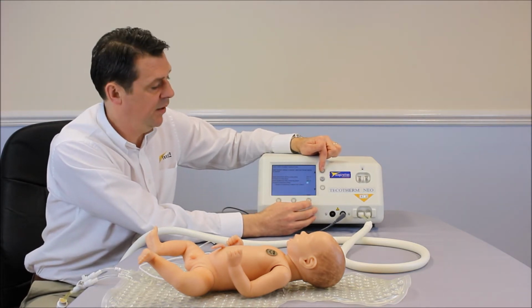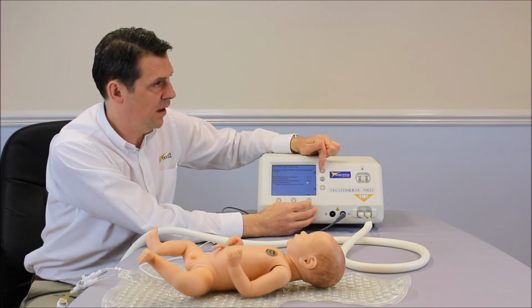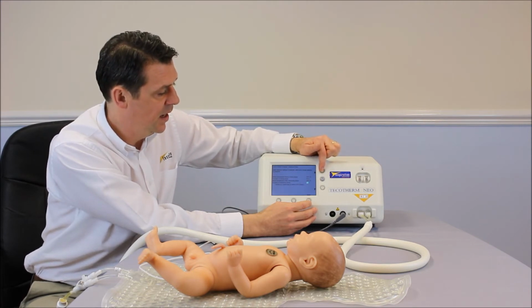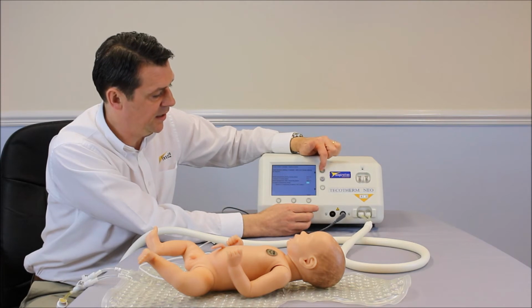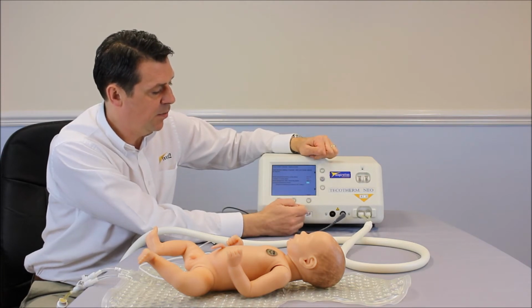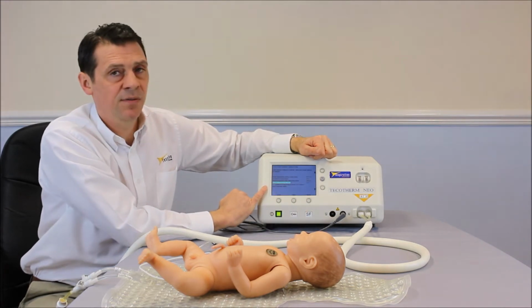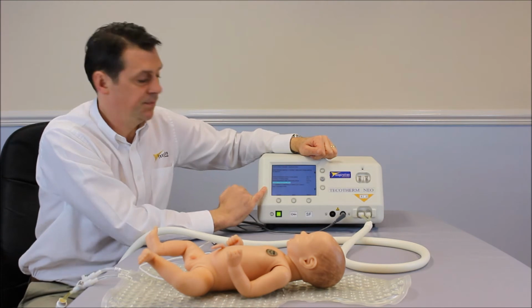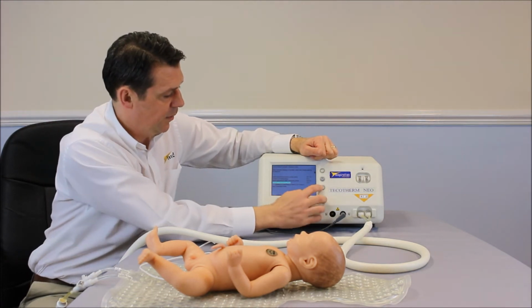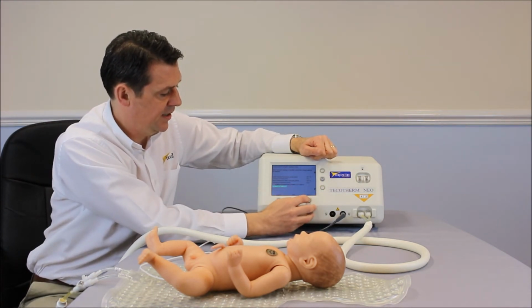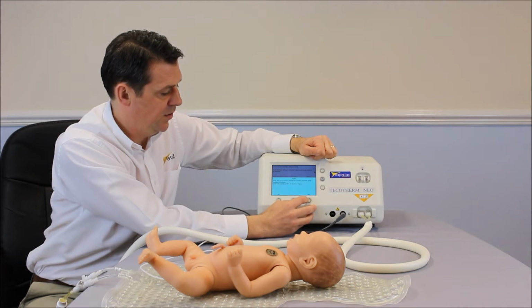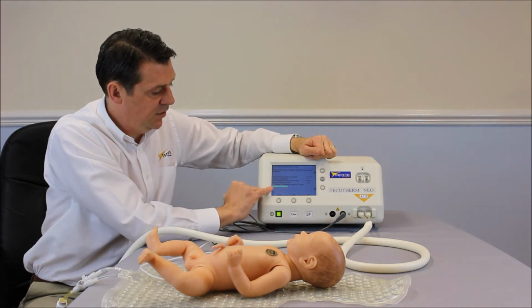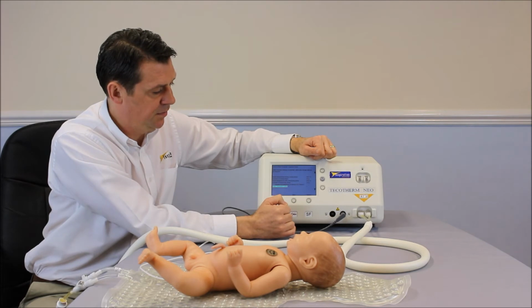Rather than 0.5 degree per hour, I can make it up to maybe down to 1/3 of a degree per hour. If I press up arrows here, I can make this go to 12 hours, and that will be 0.29 degrees per hour. Press apply. I could also save this treatment data if I wish to make this your default. If I come down, I'll do the treatment profile and press select, and that will be my new setup guide. And here we have new select treatment profile number 1.